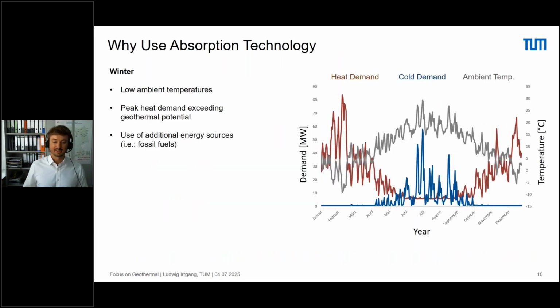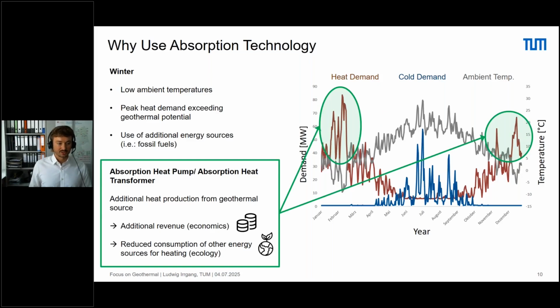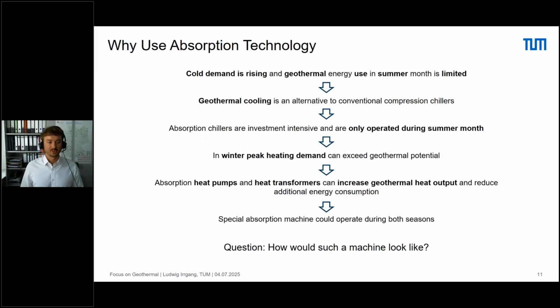If we look again at the heat demand and cold demand curves, we can identify another problem with geothermal energy: we have very high peak load in winter times, and usually these peak loads have to be covered with other energy sources, like fossil fuels. That's where we can also use absorption technology - for example absorption heat pumps or heat transformers - to increase heat production from the geothermal brine, increasing revenue and decreasing consumption of fossil fuels.